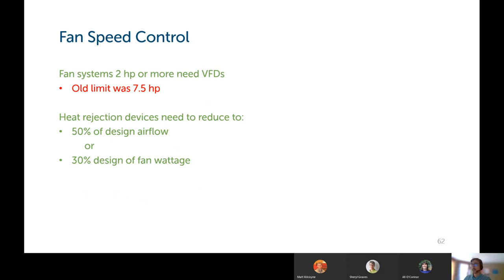Fan speed control: fan systems 2 horsepower or more need to have VFDs. The limit in the old code was 7.5 horsepower, so this has been reduced to include more fan systems. Heat rejection devices need to reduce down to 50% of the design airflow, or 30% of the design fan wattage, one of those two.